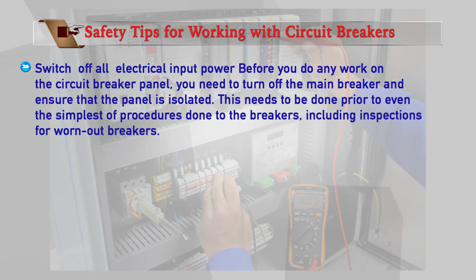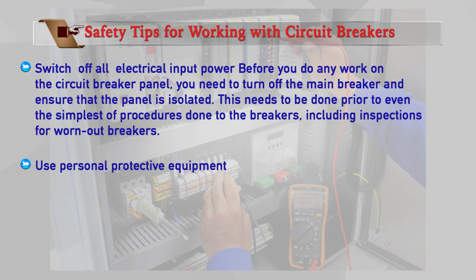First, switch off all electrical input power before you do any work on the circuit breaker panel. You need to turn off the main circuit breaker and ensure that the panel is isolated. This needs to be done prior to even the simplest procedure on the breaker, including inspection for a worn-out breaker. Use personal protective equipment.